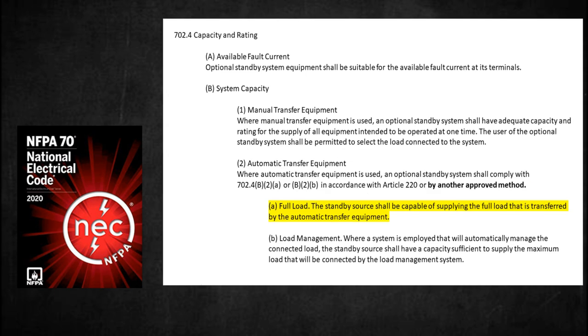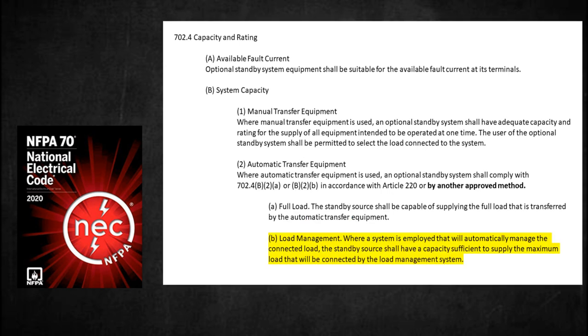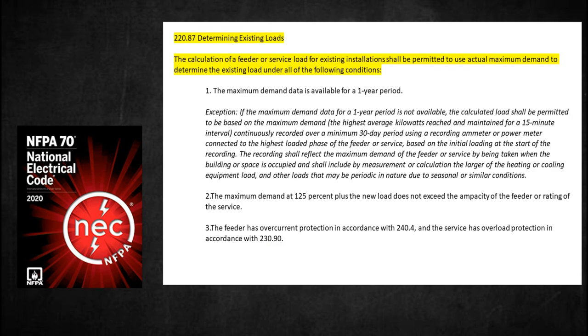For full load: the standby source shall be capable of supplying the full load that is transferred by the automatic transfer equipment. For load management: where a system is employed that will automatically manage the connected load, the standby source shall have a capacity sufficient to supply the maximum load that will be connected by the load management system. Under Section 220.87, the code states that the calculation of a feeder or service load for an existing installation shall be permitted to use actual maximum demand to determine the existing load under all of the following conditions.